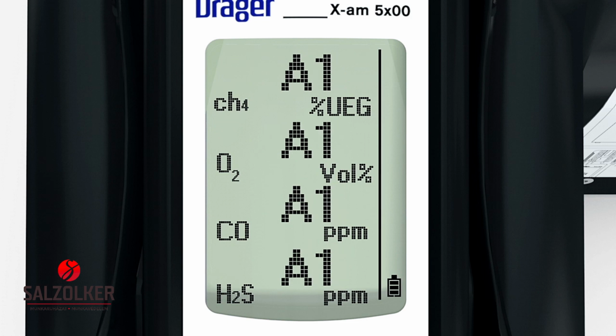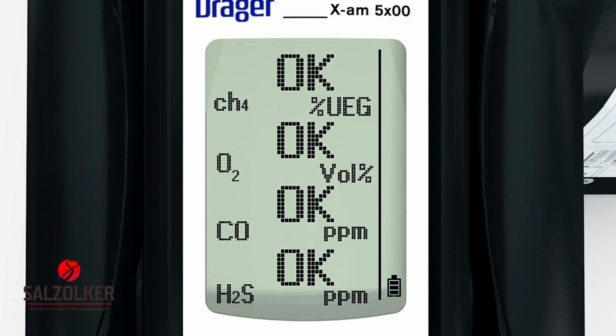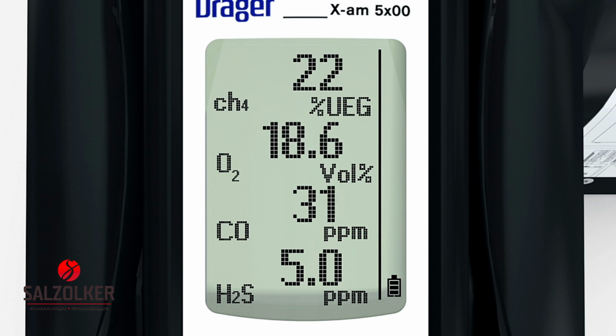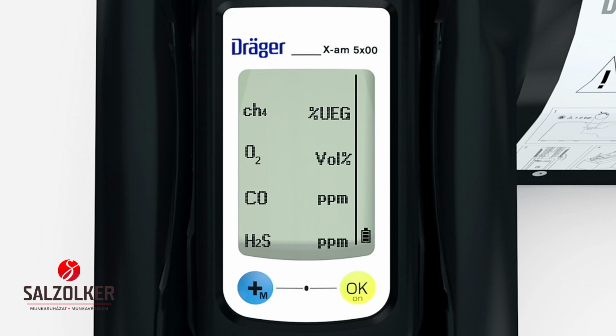If the function test is correct, a flashing OK will appear in the display. The function test is now complete. If an error occurs during the function test, a channel error will be displayed for the sensor or sensors. The device will have to be calibrated and possibly repaired.